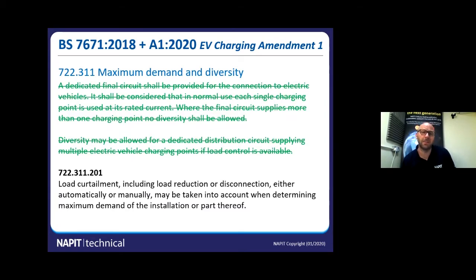And the first one here is maximum demand and diversity. Now, we used to have to look at the full rated current of the EV charging device, look at our maximum demand and see if there was enough spare capacity to install our charger. We couldn't use diversity if we had multiple points. So it was quite restrictive, really. And with the government wanting to push these charge points out there and everybody wanting to go green, it was quite unhelpful.